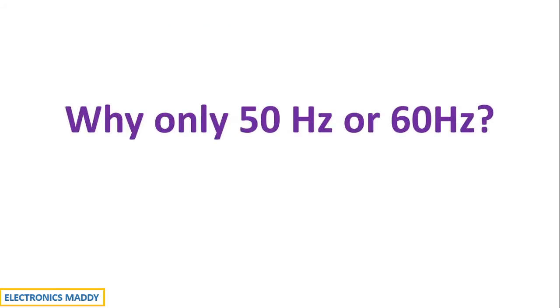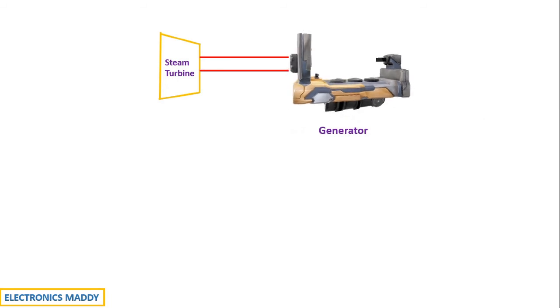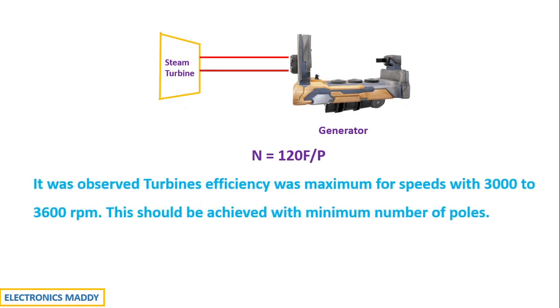But why only 50 Hz or 60 Hz? As I mentioned previously, the turbine drives the generator as shown through a prime mover. We know that N is equal to 120 F by P. From studies, it was found that turbines operate at maximum efficiency at speeds of 3000 rpm to 3600 rpm. This should be achieved with minimum number of poles because the construction cost of the poles are very high and hence this adds up to the overall cost of the system. So, the objective is to reduce the number of poles.